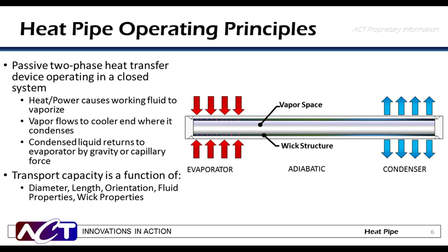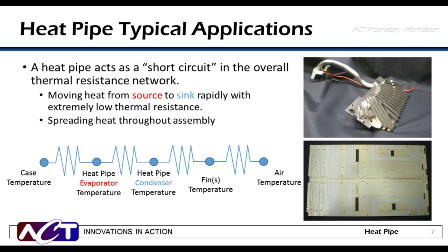A heat pipe is a passive two-phase heat transfer device that operates in a closed loop. Heat generated by components causes a working fluid to vaporize inside the pipe. That vapor flows to a cooler end of the pipe where it condenses, giving off its heat. The condensed liquid is then returned to the evaporative region by gravity and/or capillary forces. The transport capacity of a heat pipe is a function of the diameter, the length, its orientation with respect to gravity, the working fluid properties, and the wick properties.